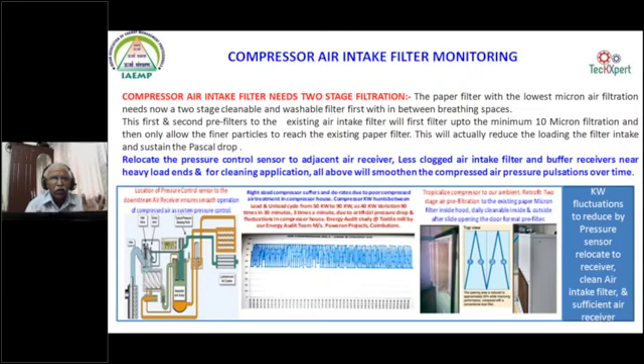At the same time, if it is, let us say, 3,000 hours, you have to replace the filters. Within 5,000 Pascal is, let us say, the maximum pressure drop allowed. If the pressure drop goes more than 1,000 Pascals, you can immediately remove the pre-filter and clean it, either daily or weekly, depending on the industry requirement. Keep the existing paper filter very clean and neat. Let us not overload the paper filter, and let us keep the pre-filters clean daily. You can see that the FAD is very much improved for the given compressor.